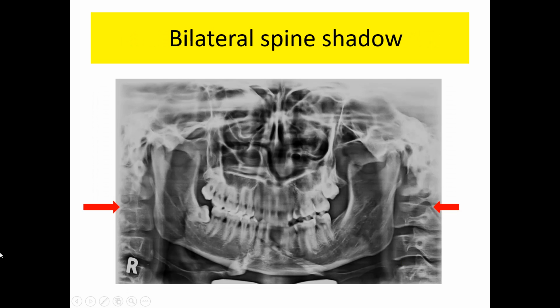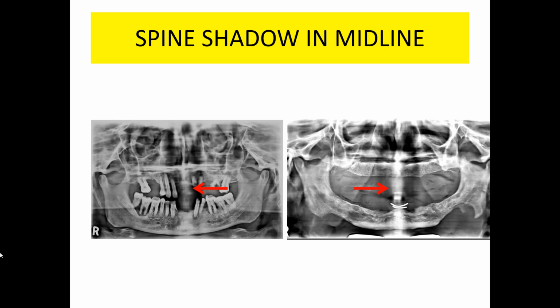As you know, spine is also in the midline. It falls into the focal trough twice, so it is portrayed as if split vertically in half in the mid-sagittal plane with each half folded outwards. Both images are real images and not ghost images as some of you have thought. Spine also casts a shadow centrally to obscure the anterior part of the jaw. With newer machines, this error is minimized as exposure factors are adjusted when the beam moves through this area of spine. In an edentulous mouth, as seen on your right hand side, it can be better appreciated.